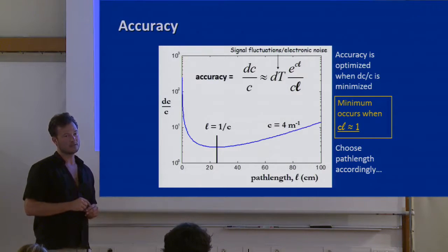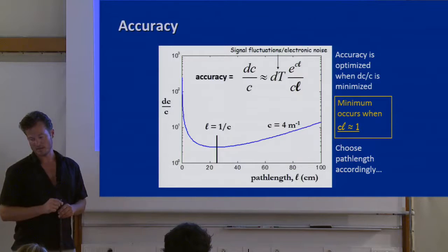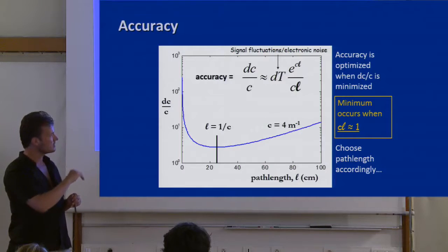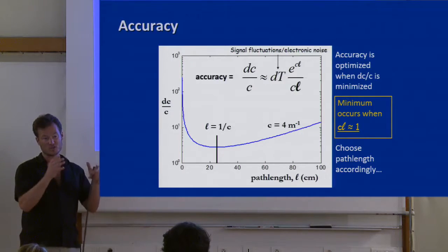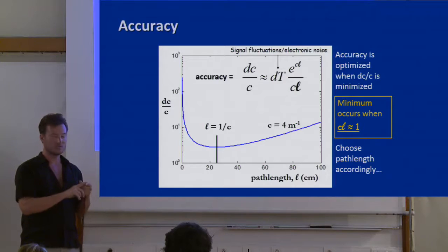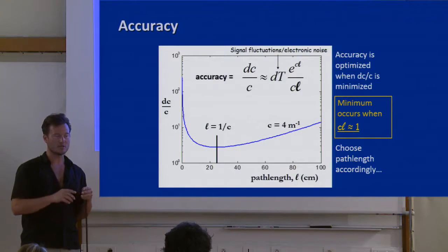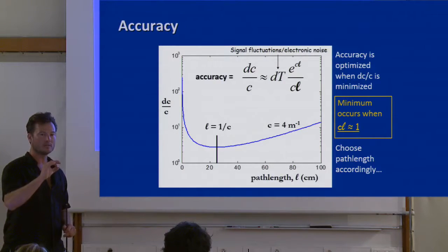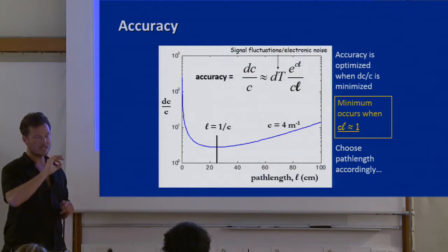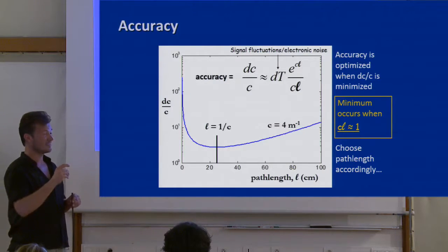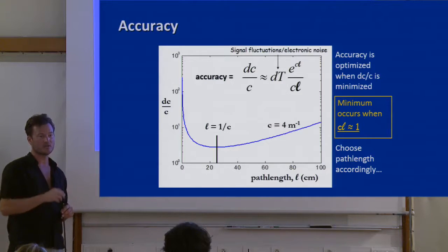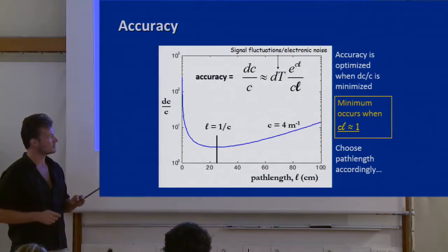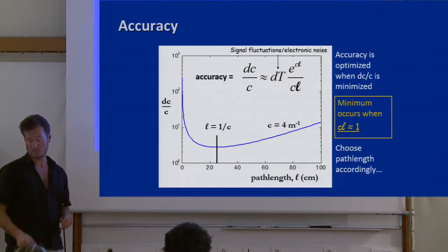And I definitely say that we've been spoiled over the years because the AC9, in terms of accuracy, is really an incredible instrument. The fact that it goes in the water, you have to worry about pressure changes, temperature changes, salinity changes, all the things that we talked about yesterday. And it still gives us 0.001 or less just random noise. And our bias errors, we can get to 0.002 to 0.005, which is really incredible. If you ever try to make these measurements on a benchtop spectrophotometer with a 10 centimeter path length, usually you can't come close to what an AC9 can do. It's pretty amazing.